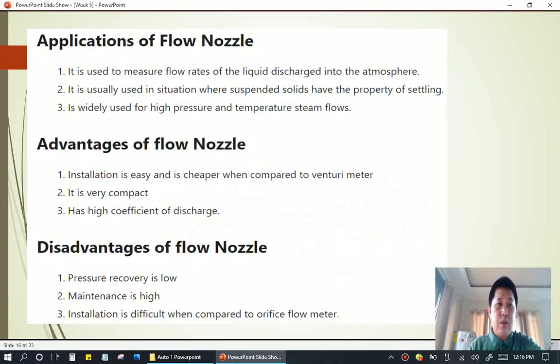So we have here the application of the flow nozzle flow meter. It is used to measure flow rates of the liquid discharge into the atmosphere. It is usually used in situations where suspended solids have the property of settling. It is widely used for high pressure and temperature steam flows.